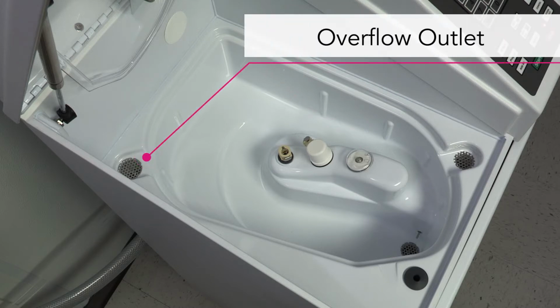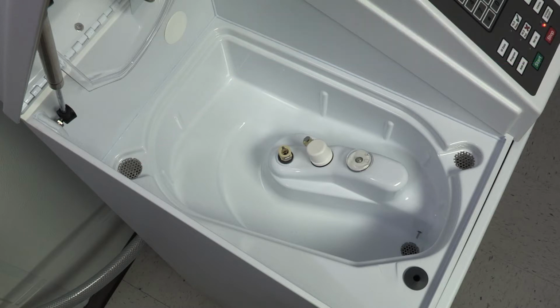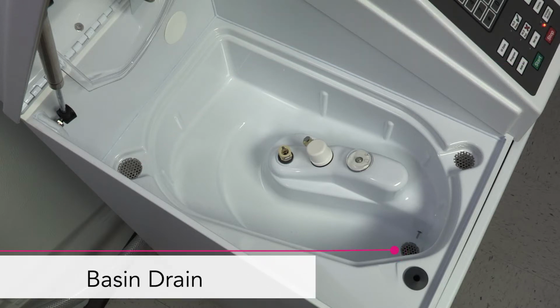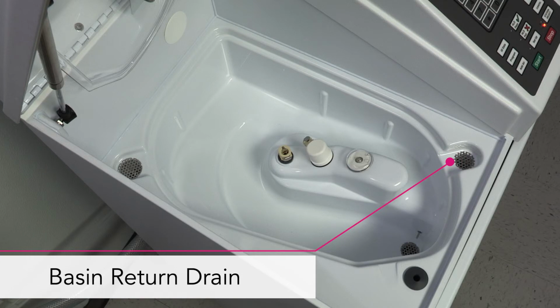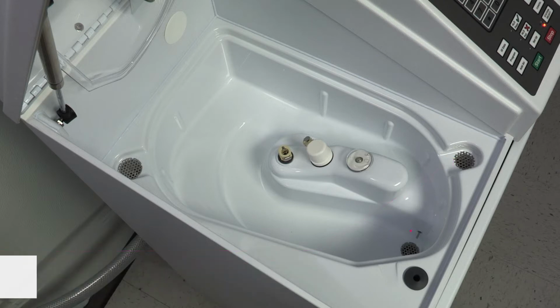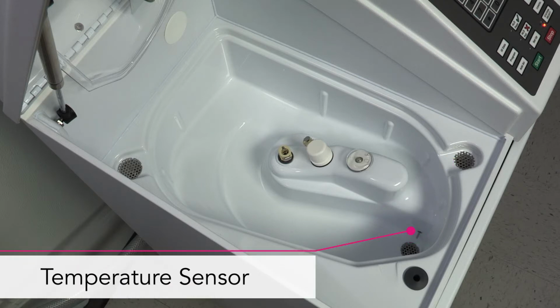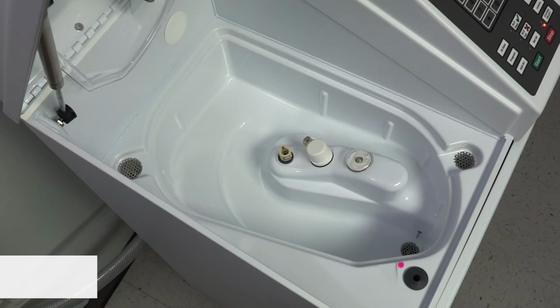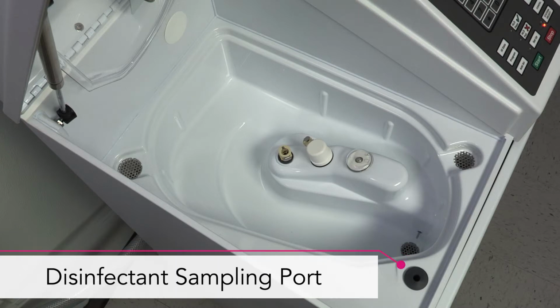The overflow outlet will drain excess fluids if necessary. Waste fluids are discarded through the basin drain. The basin return drain allows for recirculation of the disinfectant through the disinfectant filter. The temperature sensor monitors the disinfectant temperature to ensure Rapicide PA disinfectant is between 30 to 40 degrees Celsius. If the temperature is outside of the required range, the unit will stop and an alarm will sound to alert the operator to the temperature error. Each station has its own basin with disinfectant sampling port.